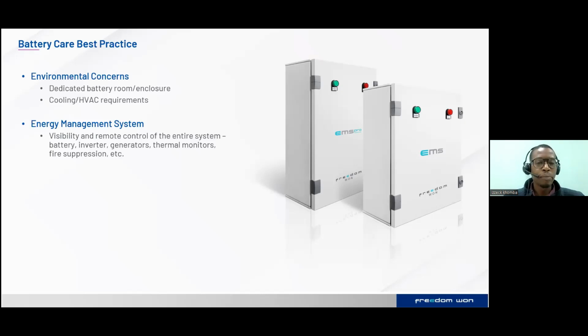And these consist of your inverters, batteries, your fire suppression system, and your energy management system integrated into a 12-meter container. Then some of these containers are deployed in remote areas, and it's difficult to actually access these areas. You travel a long distance to reach the site, and it's very critical to have your monitoring system to be able to diagnose, control, and also integrate the system. So EMS allows you to have that monitoring ability to run diagnostics without you being on site, and also change certain parameters. If there's a change in environmental conditions, then you are able to adjust certain parameters, and it gives you that flexibility to control your system.